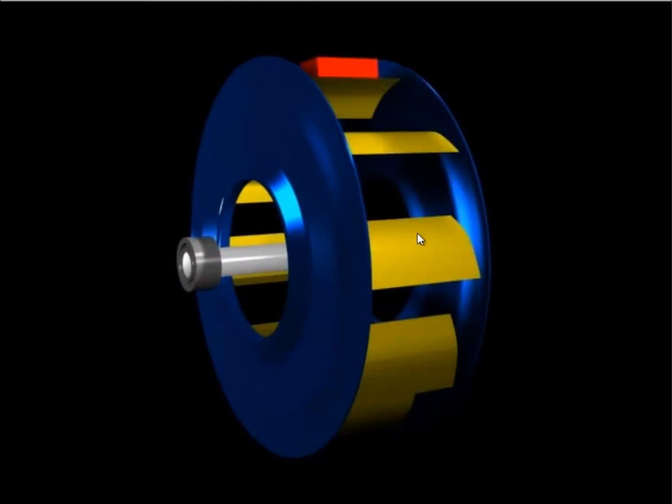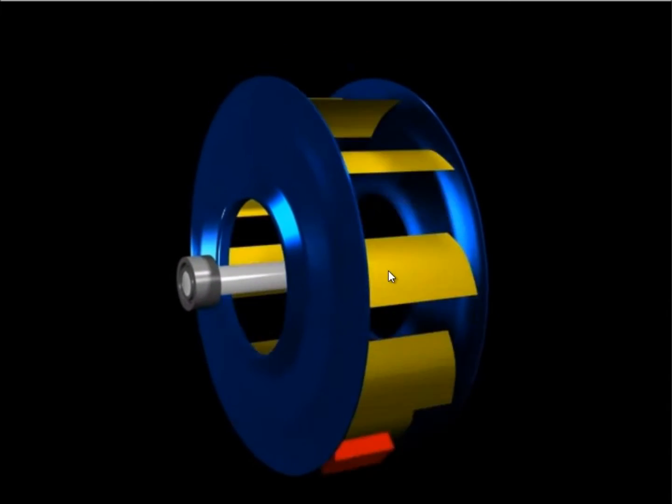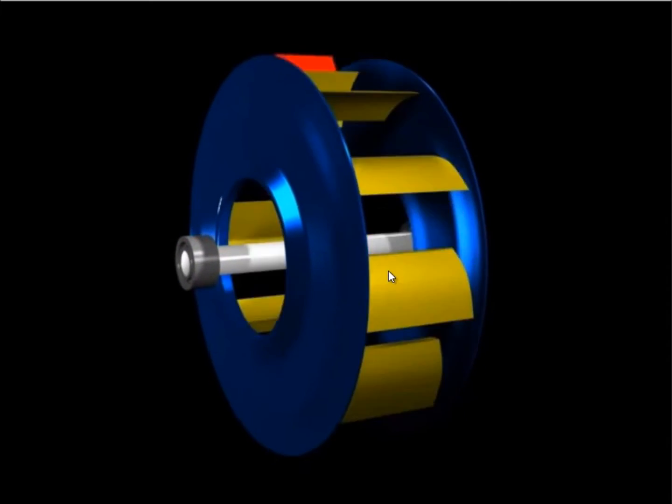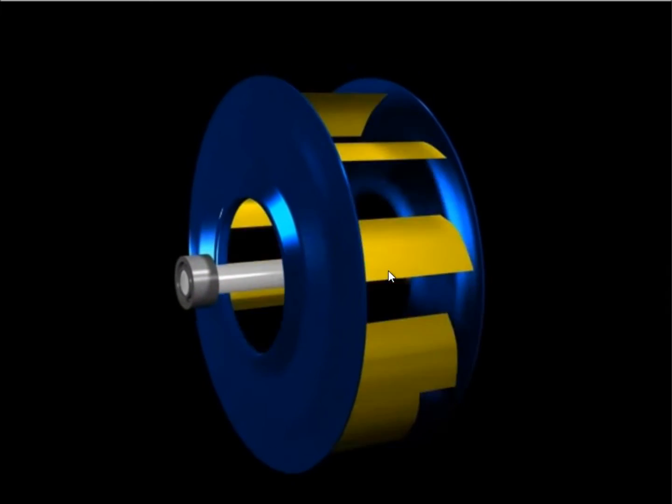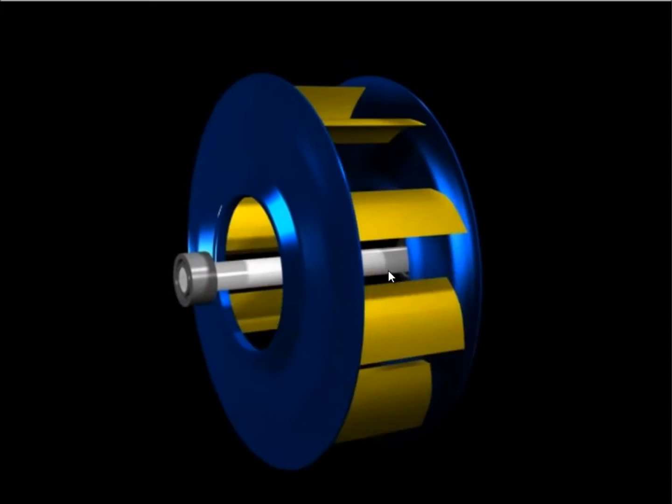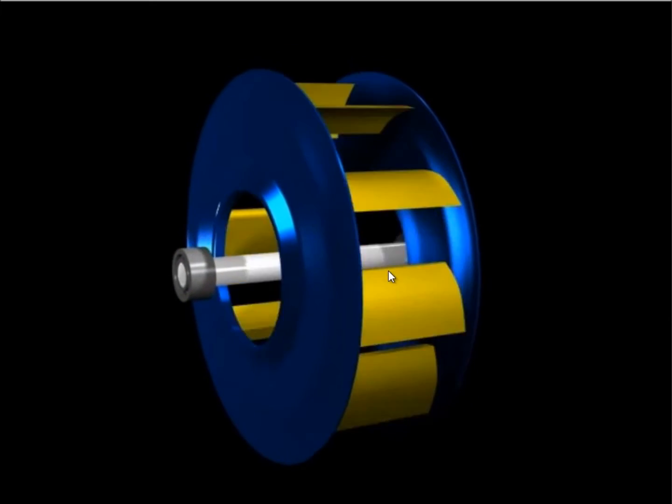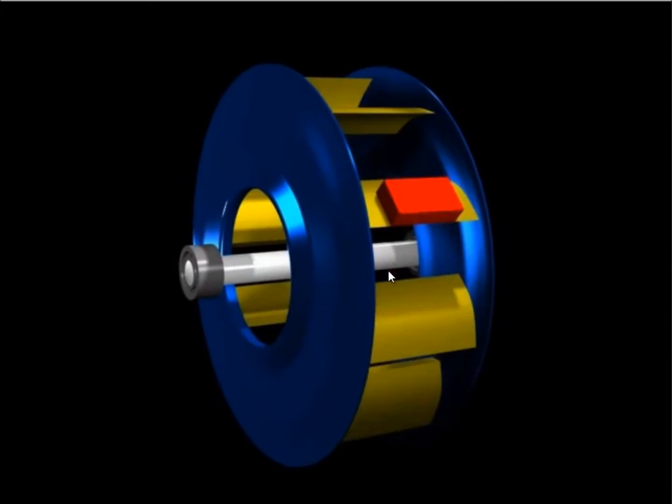Notice also in the case of static unbalance that the two ends of the rotor are moving up and down and from side to side in sync, so there's zero phase difference between the ends. Now it might not be exactly zero when you do this test, but it's close enough that you can say it's static unbalance. And knowing that means you can do a single plane balance.